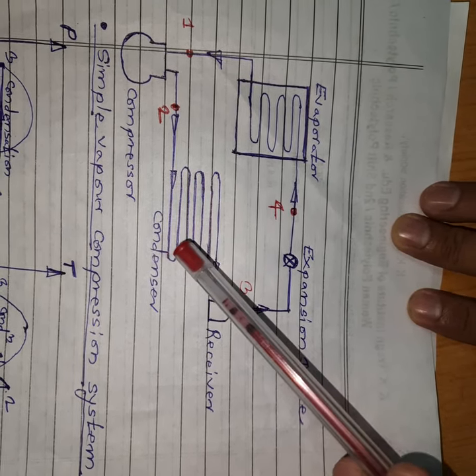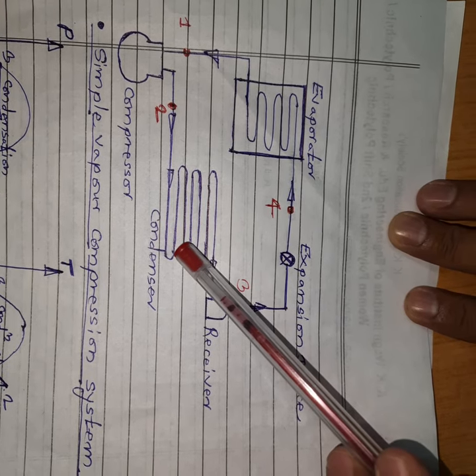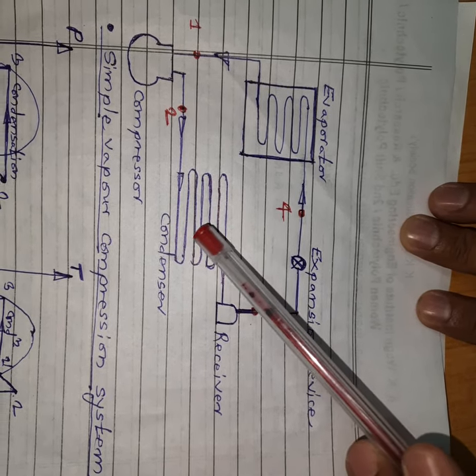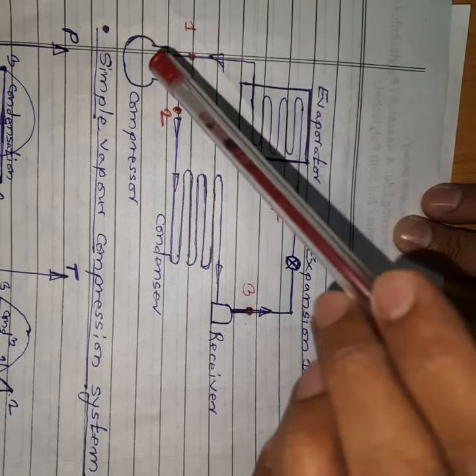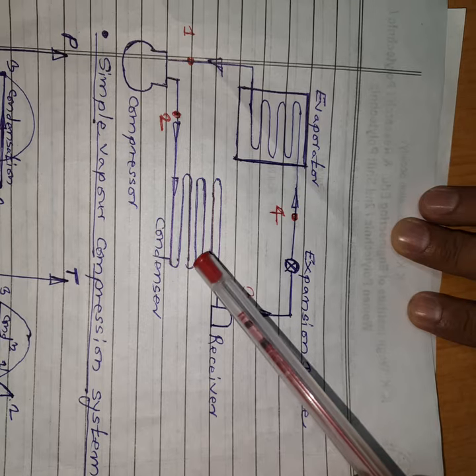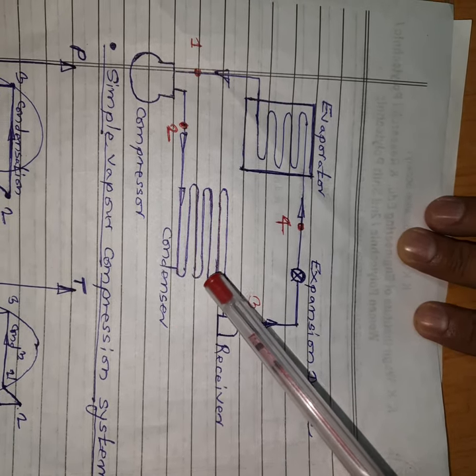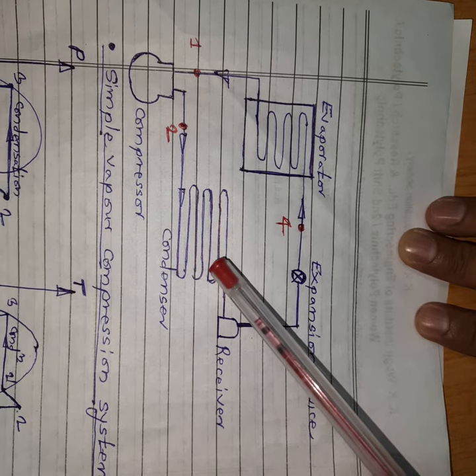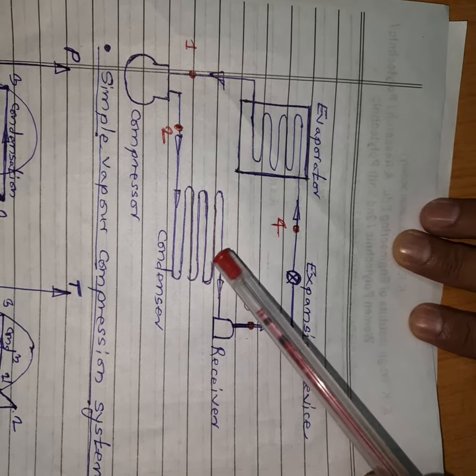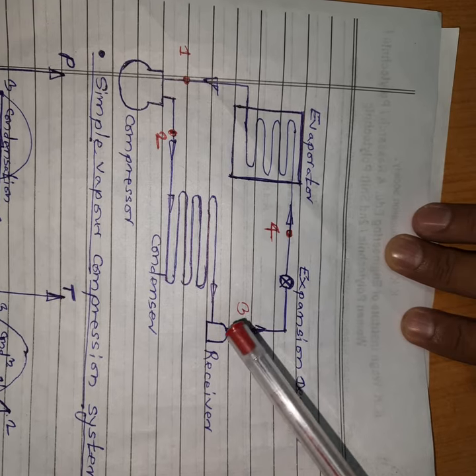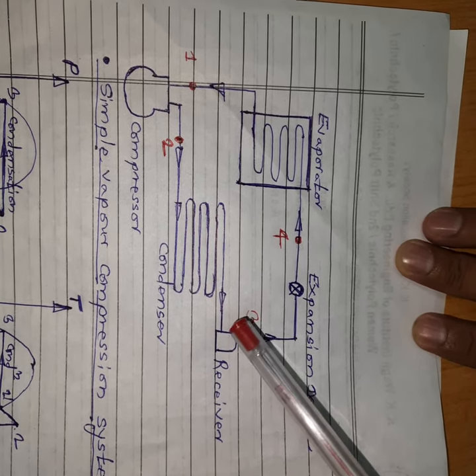In the condenser — either air-cooled or water-cooled — the heat absorbed in the evaporator and the heat added in the compressor is rejected to the atmosphere. There is a phase change in the condenser: vapor refrigerant is converted into liquid refrigerant. Leaving the condenser, it is high pressure, normal temperature liquid refrigerant.